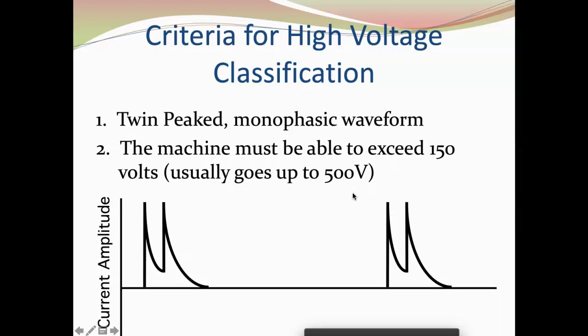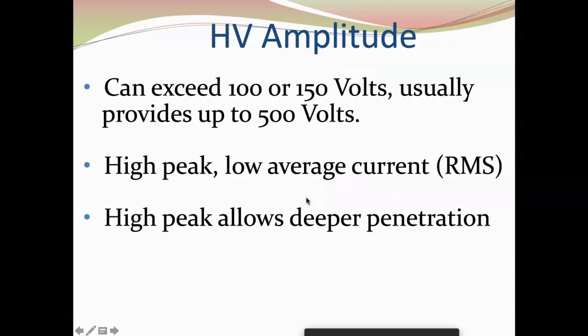It's twin-peaked and monophasic — you'll need to know that for the board of certification examination. As we progress, we know that high volt can get up to a relatively high amplitude — about 500 volts, give or take. This is the first device we're talking about that is capable of delivering greater than 100 to 150 volts during the electrical treatment. The other thing we know is that we have these high twin-peaked waves, but there's a low average current, and we'll talk about why the average current reduces.